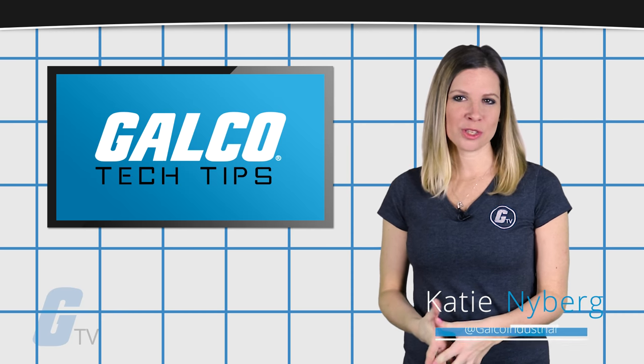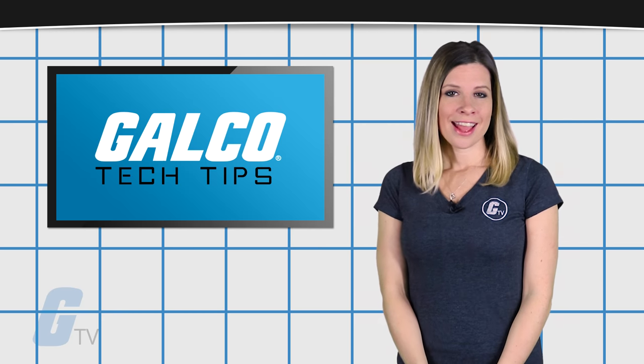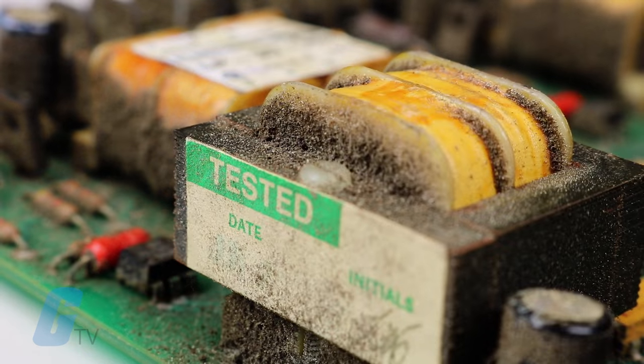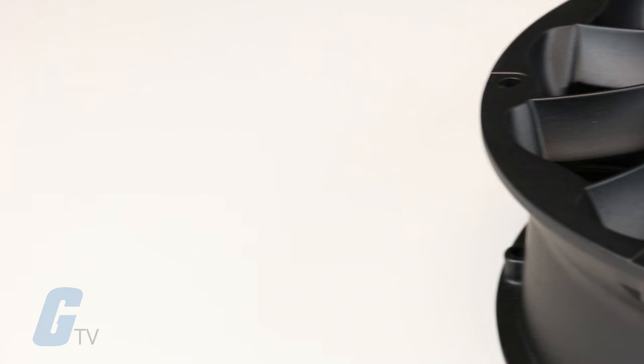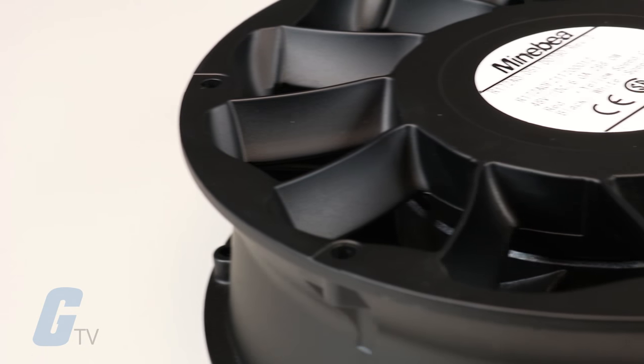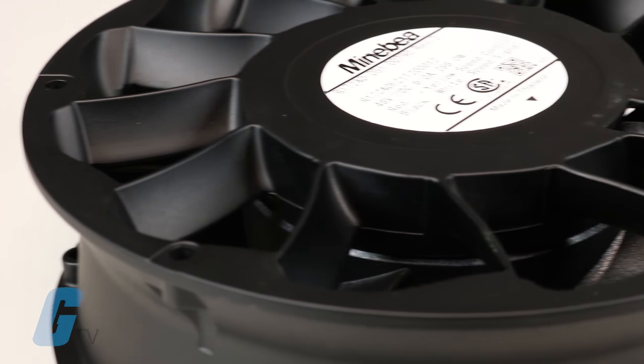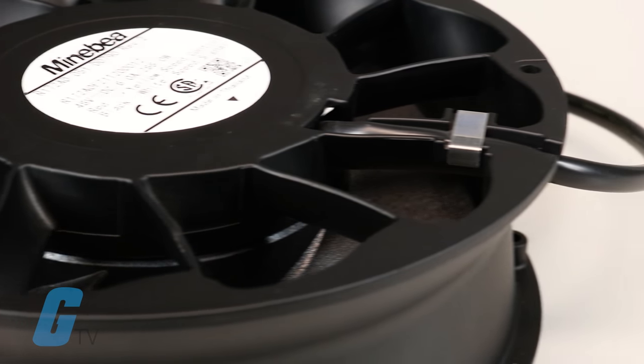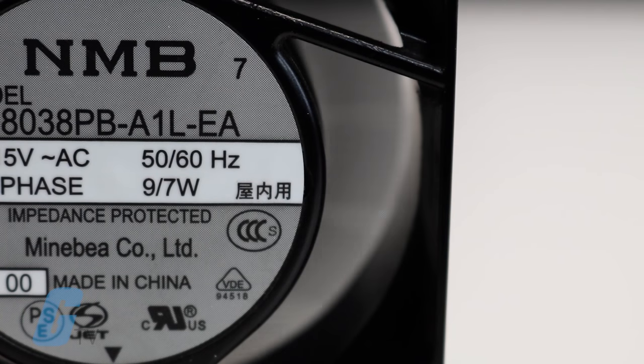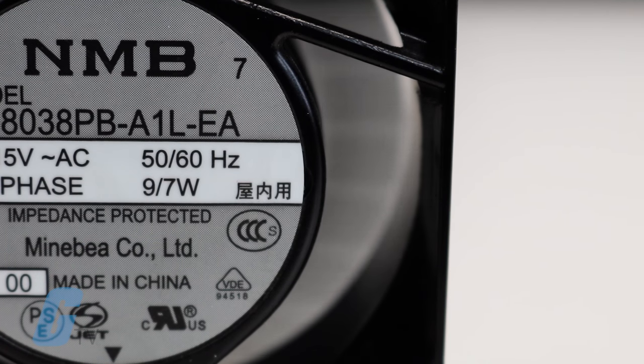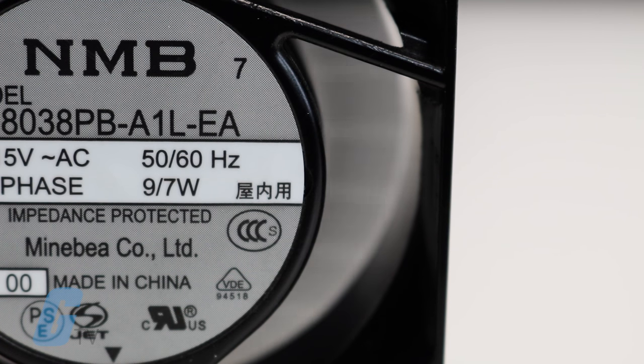Depending on your environment, drives and other components can accumulate contaminants over time. Dust or dirt buildup in cooling fans can quickly derate a component's ability to keep itself cool by restricting the airflow and adding to the amount of heat within the component. The problem is even more severe in the event of oil contamination.